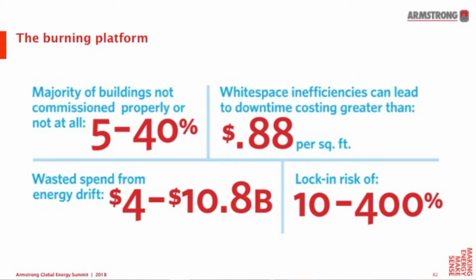There are many factors that lead to loss of energy savings potential in a building. We found that the majority of buildings are not commissioned properly, which leads to anywhere from 5 to 40% loss in energy savings potential. Also, Peter mentioned the drift—drift can be at least 10 to 30% in 1 to 2 years. Surprisingly, that accounts for close to about $11 billion in wasted energy just in the US. That's a tremendous amount of energy.